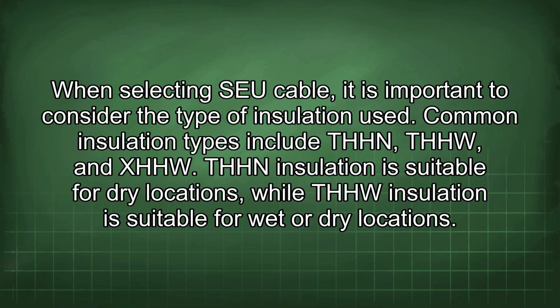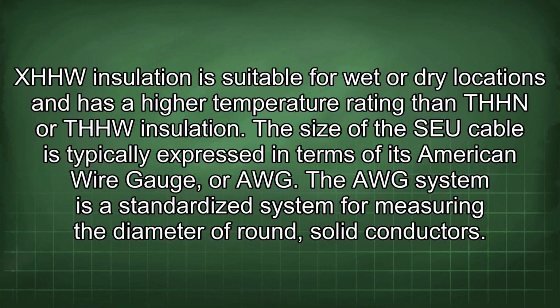When selecting SEU cable, it is important to consider the type of insulation used. Common insulation types include THHN, THHW, and XHHW. THHN insulation is suitable for dry locations, while THHW insulation is suitable for wet or dry locations. XHHW insulation is suitable for wet or dry locations and has a higher temperature rating than THHN or THHW insulation.